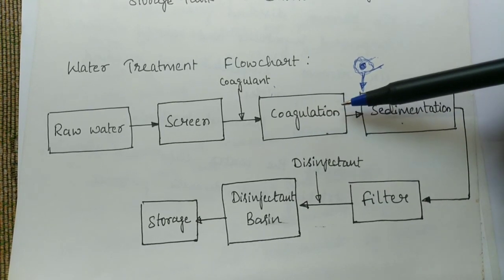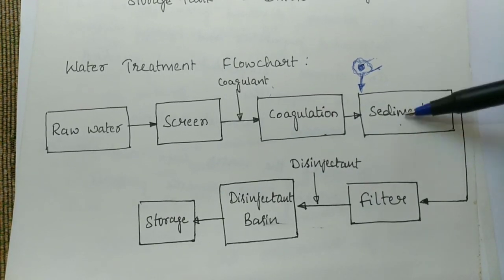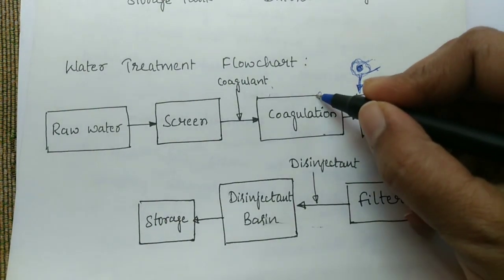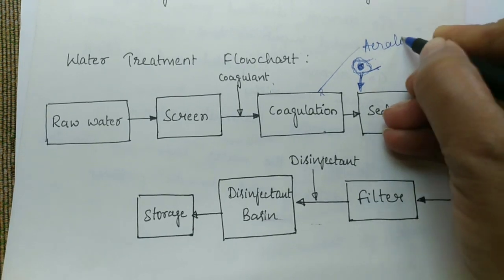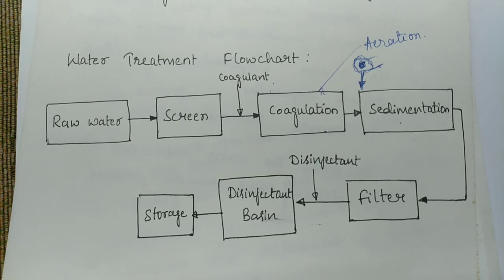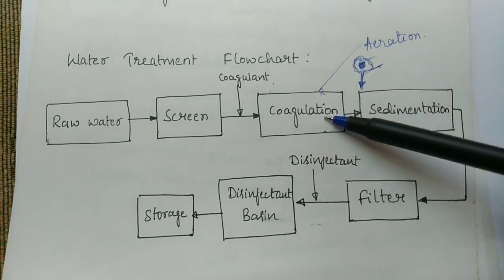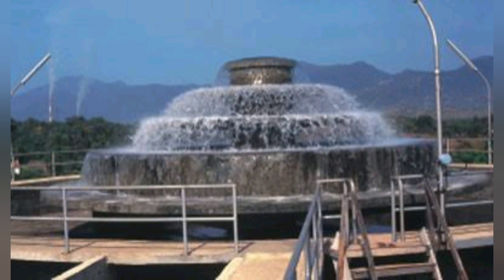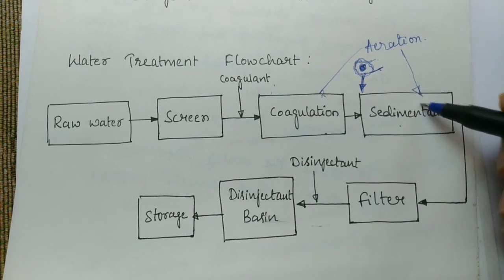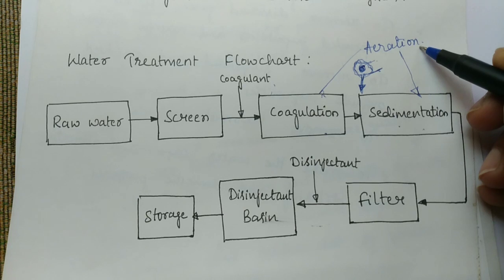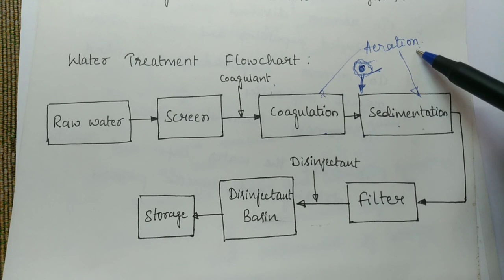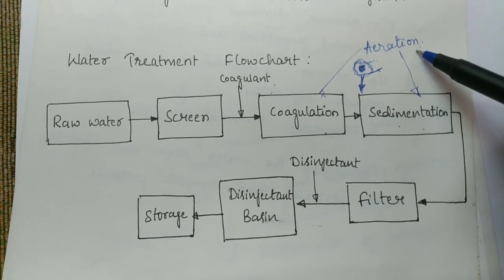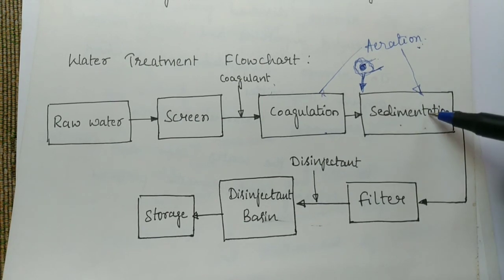The coagulant forms the floc, and then this water is taken to the sedimentation unit. Before sedimentation, we can also provide an optional treatment called aeration. Aeration is a treatment wherein we aerate the water by increasing the dissolved oxygen content. Water can be taken directly from coagulation to sedimentation, or first taken to aeration and then to sedimentation. Aeration increases the oxygen content making the water fresh, helps in removing various dissolved gases, helps in removing iron and manganese salts, and purifies the water to some extent — even some color gets removed in the aeration process.